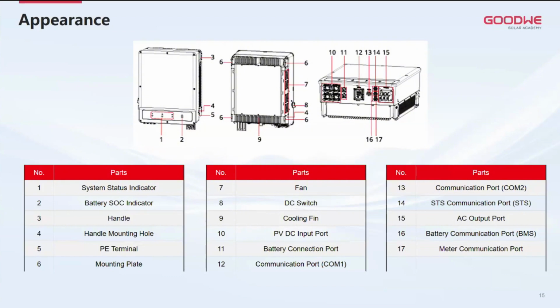So it's a smart fan. This is actually to reduce the noise, or the decibels, that come from the inverter during operation. So there are more ports to connect to: the PVs for the MPPTs, the battery connection port, the communication connection port for paralleling, and even the smart load controls and the lights, the diesel generator start-stop signals, and the AC port output to the STS. Though, this is just a summary.